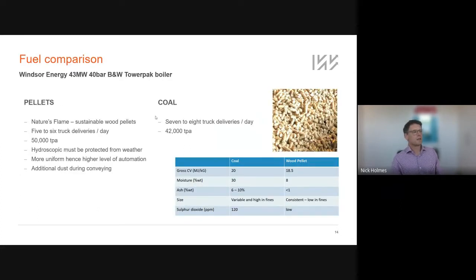So the fuel available is pellets that are produced by a company called Nature's Flame. They manufacture their pellets using geothermal energy. So it's a carbon neutral product. Massive reduction in truck movements onto the site. So the big differences between the coal and pellets are the moisture content. Wood pellets are a lot drier. They have significantly lower ash. Their calorific value is a little bit lower, so that it does need to be offset with slightly higher tonnage rates. But obviously, a far, far better fuel to use.